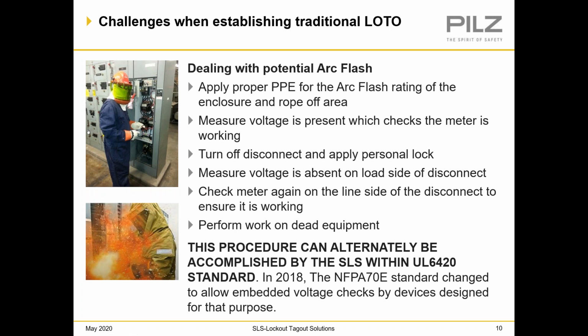The mechanic or the technician will have to don personal protective equipment specifically used for arc flash when he's actually testing that there's 0 voltage within the panel that he's locking out, or she. The tech would measure voltage is present, checking the meter that it's working, turn off the disconnect and apply a personal lock. Measure voltage is absent on the load side of the disconnect. Check meter again on the line side of the disconnect to ensure that it is working. And if all that shows 0 voltage in the system, then the work can be performed on the dead equipment.